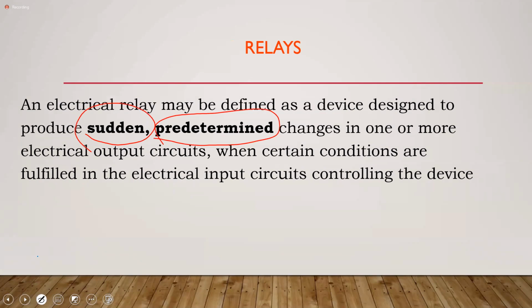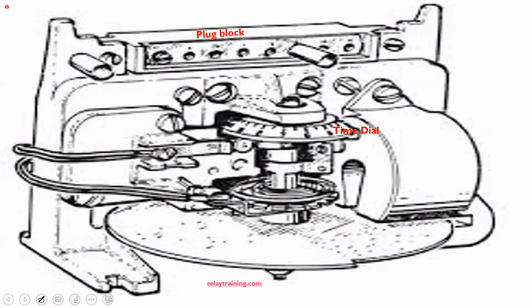All right. So in other words, what we're talking about is predetermined. We have determined that the relay will operate when it sees 2 amperes or 3 amperes. Okay? Okay, sir. Now, that determination is based on what we select up here. So that's what we call the plug setting. The plug setting, which is also referred to as the tap setting, because when I select one of these, all I'm doing is tapping off a winding. So it's a long winding, yes? It's a winding in there, and each of these points, each opening, represents me tapping off a portion of the winding.